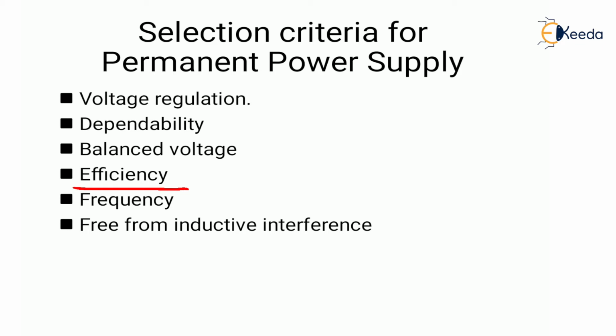Next point is efficiency. The efficiency of the system should be good, because efficiency is nothing but output upon input, and the efficiency will be low if losses are more. The losses in the line and machineries largely depend upon the power factor, and therefore it is important that consumers having loads of low power factor should be penalized. Loads of low power factor also require greater generator capacity and produce larger voltage drop in the lines and transformers, which affects the efficiency.